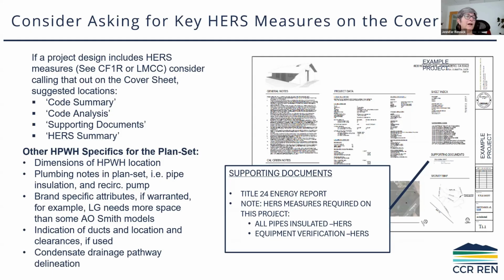I don't know if that's come up for you guys, but we've had a few projects where the builder knows the heat pump water heater has to go in, but folks don't realize it has condensate. Even one of the local plumbers I thought knew all this, we were just talking about how to run better piping, and I mentioned that some folks don't even know you have to deal with the condensate.